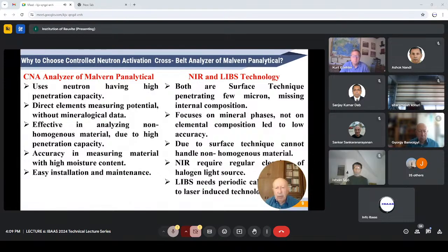Why choose the controlled neutron activation cross-belt analyzer? It uses neutrons having high penetration capacity, directly measuring elements without mineralogical data. It is effective in analyzing non-homogeneous material due to the high penetration capacity, has accuracy in measuring material with high moisture content, and is easy to install and maintain.